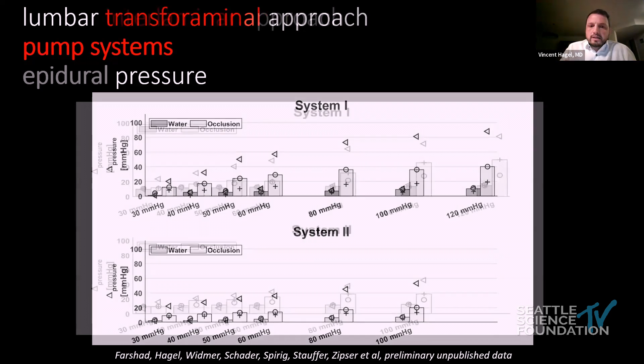If we look at system two, the spine certified pump in the lower part of the slide, then obviously, even if we have the maximum setting of 100 millimeter mercury and we occlude the working channel, we still do not see epidural pressures above 20 millimeter mercury. So obviously we're safe on that side.